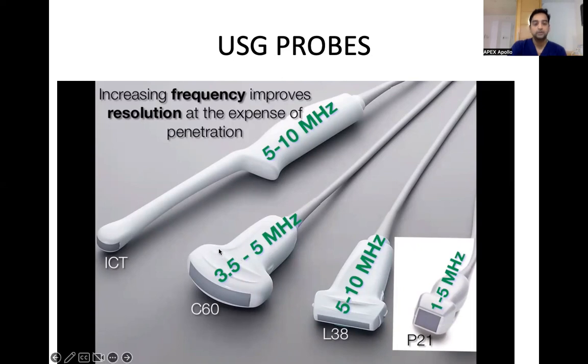For example, this is a curvilinear probe where the frequency ranges from 3.5 to 5 megahertz. Here, the 60 indicates the millimeter of the surface of the tip of the probe. This is a linear probe where the frequency ranges from 5 to 10 megahertz. And this is a phased array probe with the frequency ranges from 1 to 5 megahertz. This phased array probe is used to see deeper structures because it has good penetration with less resolution.